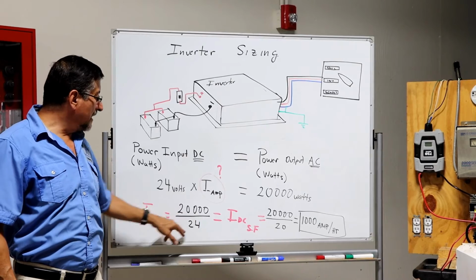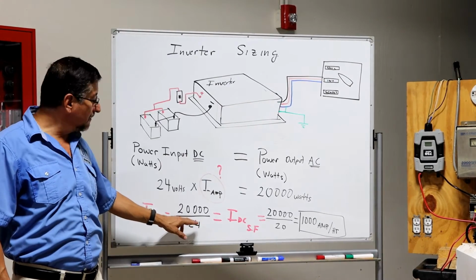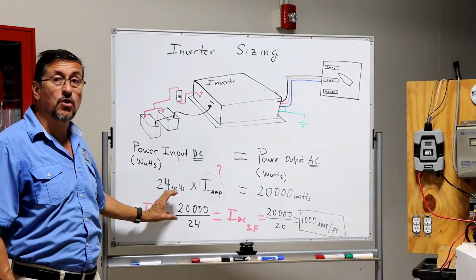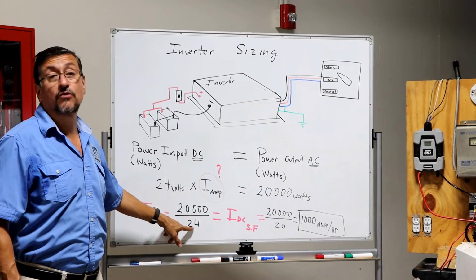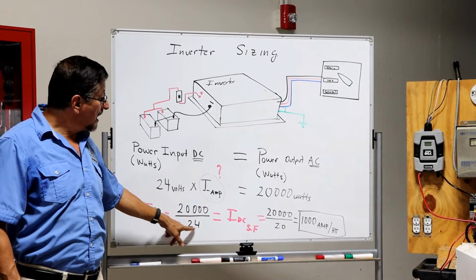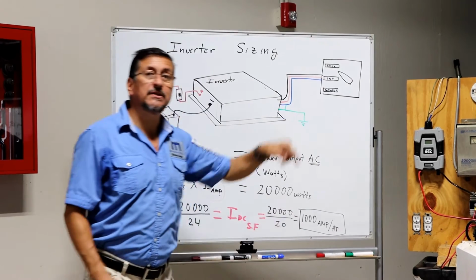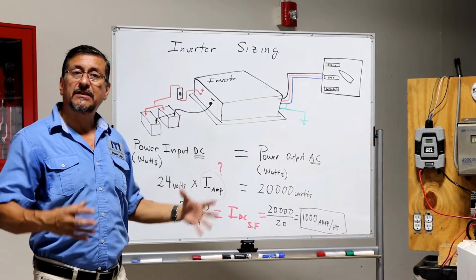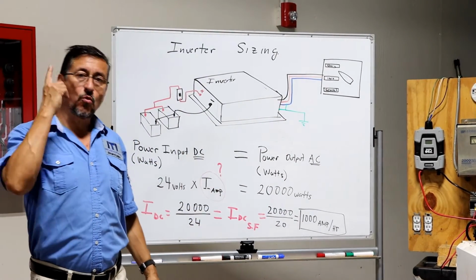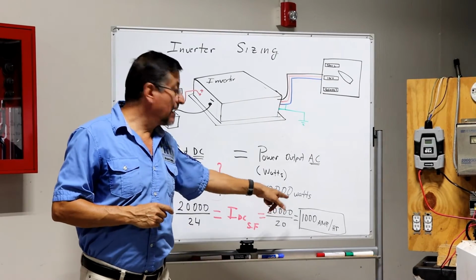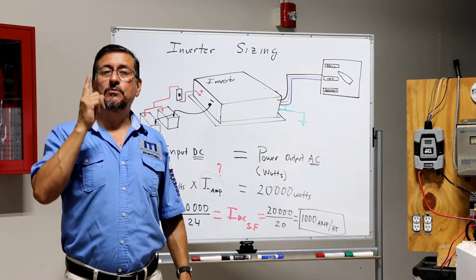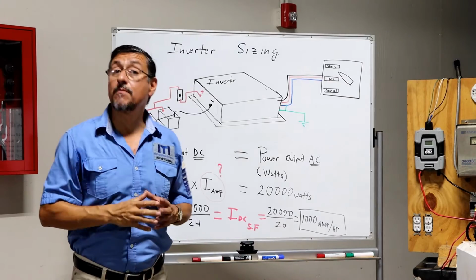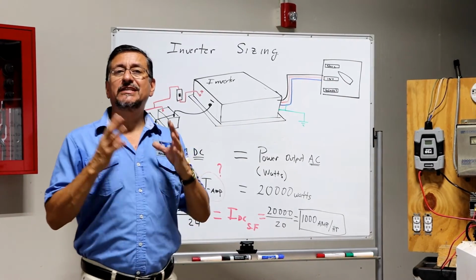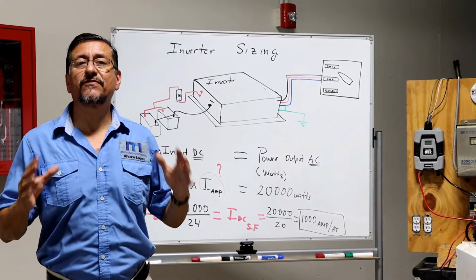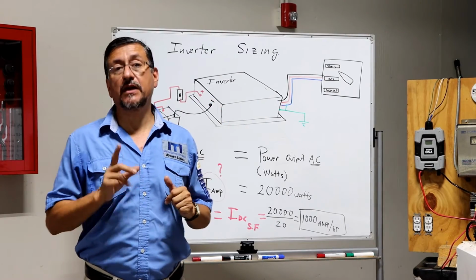Actually, I don't want to divide by 24. I'm going to divide by a smaller number in order to get more amps. I'm going to divide by 20 for safety factor. And this is the amount of amps that I need in my group of batteries to supply power for 1 hour. Remember the rule, never discharge a battery more than 50%. That's the rule. You need to be careful with that.